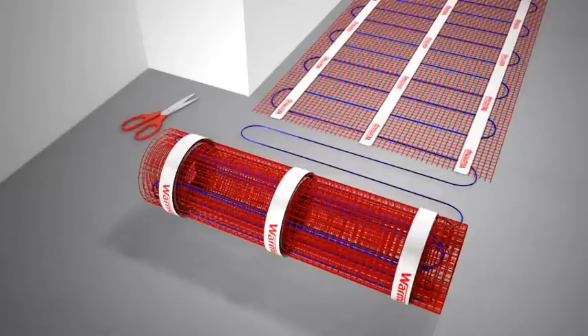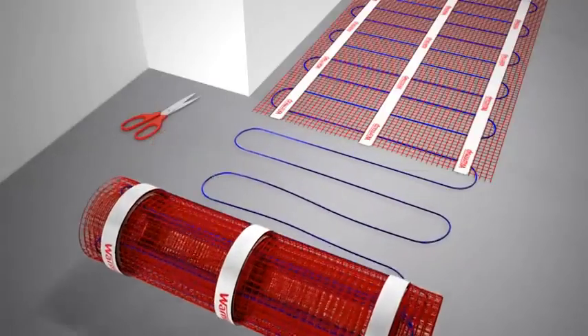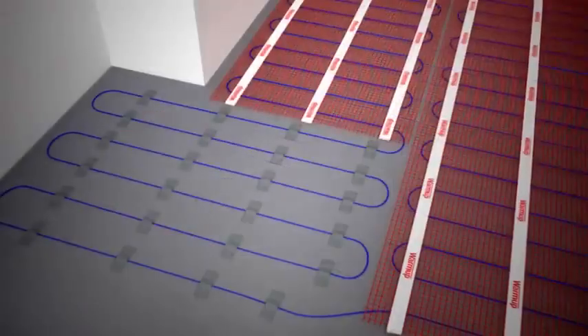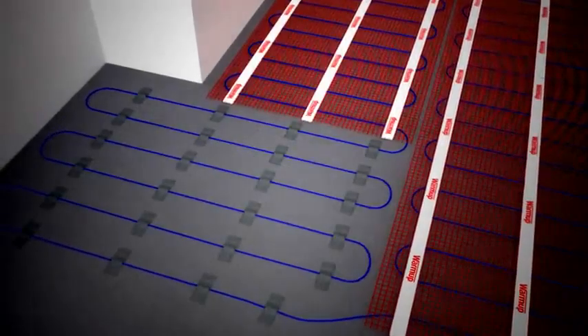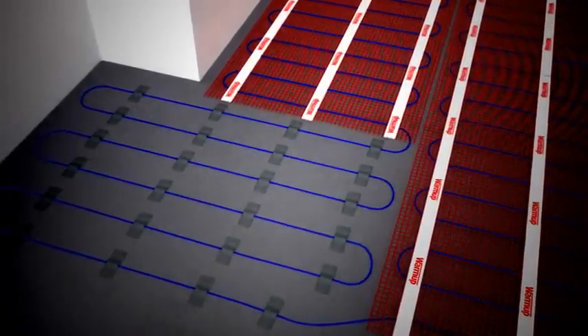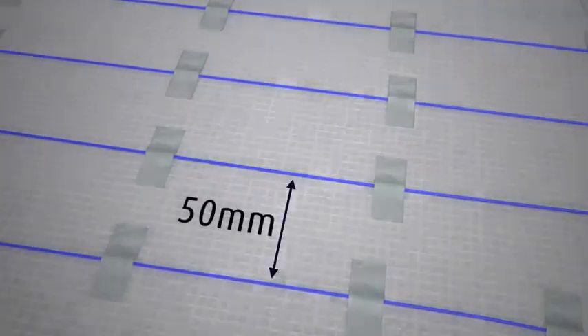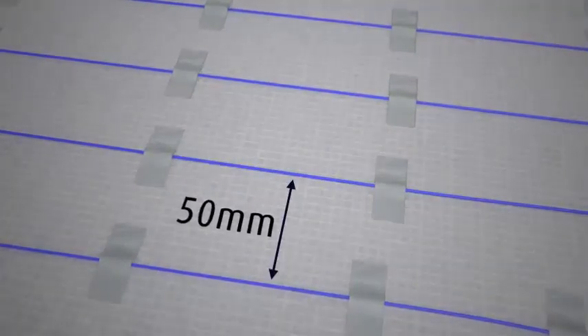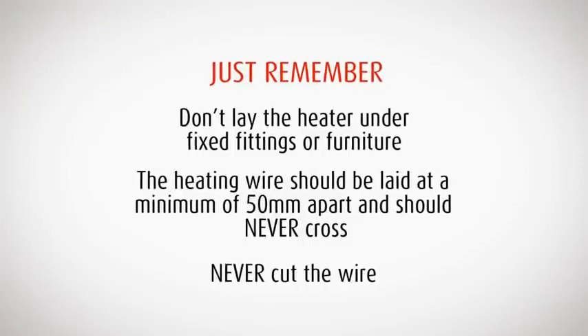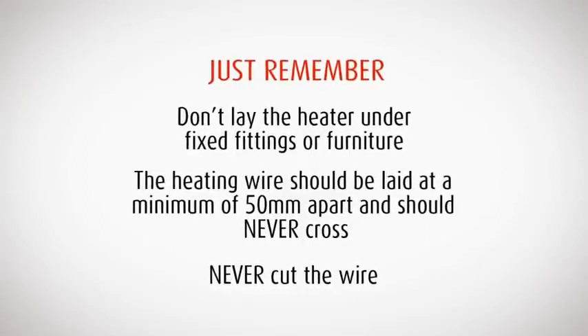When you need to cut the mat away from the wire to fit around furniture or fittings, do this taking extra care not to cut the wire. Then tape the heater wire securely to the floor using small pieces of standard duct tape. Lay the loose heater wire a minimum of 50mm apart. The wires should never cross. Just remember, don't lay the heater under bathroom furniture.